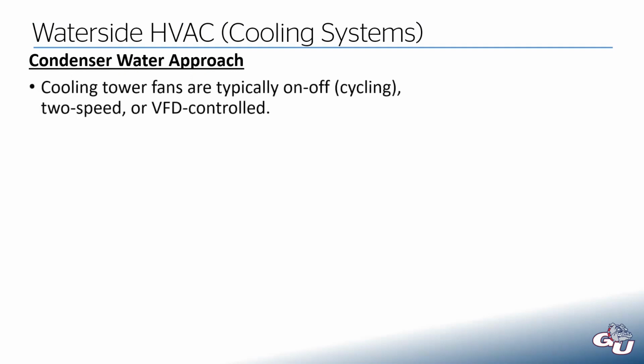Cooling tower fans. I mentioned that the cooling tower has this big fan that's moving air through that coil. That cooling tower fan, typically they're either on or off, meaning it'll cycle on to 100% speed, and then when it reaches whatever set point you set, it'll turn off. And then the water will get warmer and warmer and warmer until it kicks it on again, and that'll cool it down, and then it'll turn off again. So that would be a cycling fan. It's not great control. It leads to a lot more fluctuations in temperature because you're constantly overshooting and undershooting your set point, but that's how some of these fans are designed to operate.